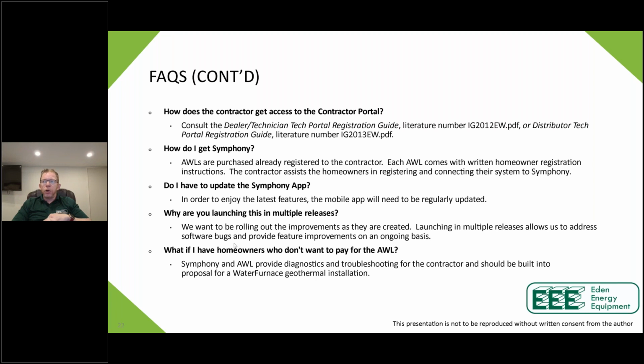What's more important is that typically it's not going to be a warranty issue. The bulk of the issues that Matt, myself, and Cody run into are either an application or installation issue, and then you get into a difficult discussion over warranty, and Matt and I try to help you make the problem go away. By using the WebLink, you're going to find out there's a problem immediately. You're not going to wait six months for the unit to have a problem that's now a failure. Because if the unit has a lockout, and you know about it and fix it in a timely fashion, you're not going to hurt the equipment.